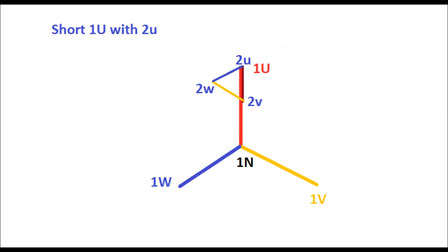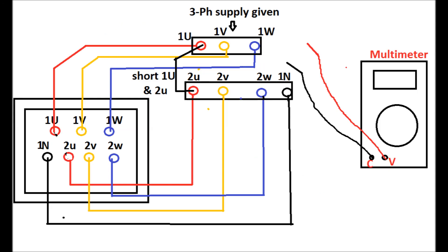In order to test the vector group of a YND1 power transformer, we first have to short the HV red with the LV red — that is, 1U with 2U. Then we have to supply a low-tension three-phase supply to the primary winding, that is 1U, 1V, and 1W. The schematic diagram for the vector group test of YND1 is shown here.